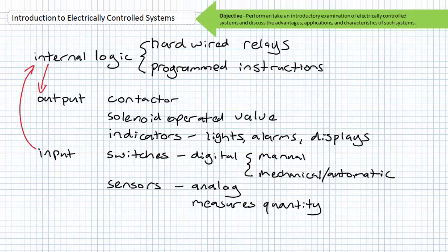However, those systems employing traditional hardwired relay-based ladder logic really are composed of physical devices, called relays, physically connected to one another in a specific manner, whereas those employing PLCs use user-defined instruction sets that mimic the function of relays. One can already see an advantage of the PLC in contrast to traditional hardwired relay-based ladder logic. To change the functionality of a system employing traditional hardwired relay-based ladder logic, one must physically rewire the system, whereas to change the functionality of a system employing a PLC, one must simply reprogram the system.